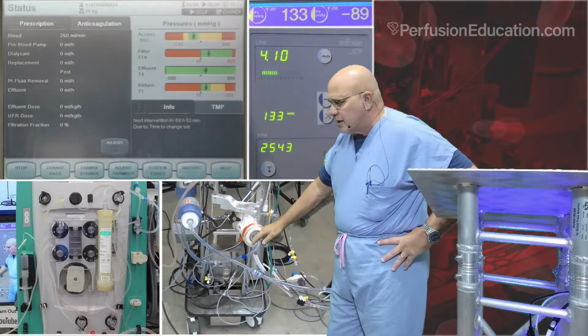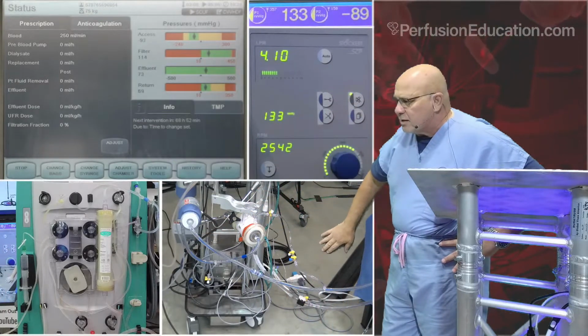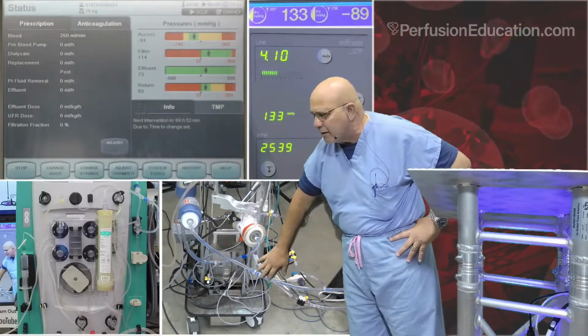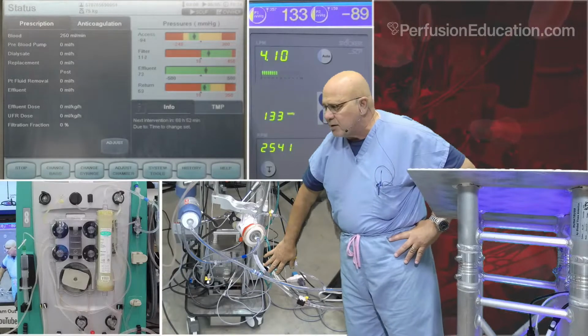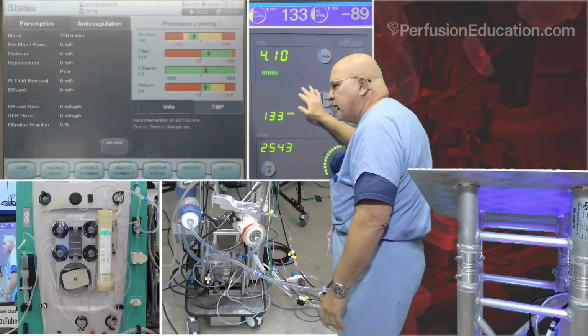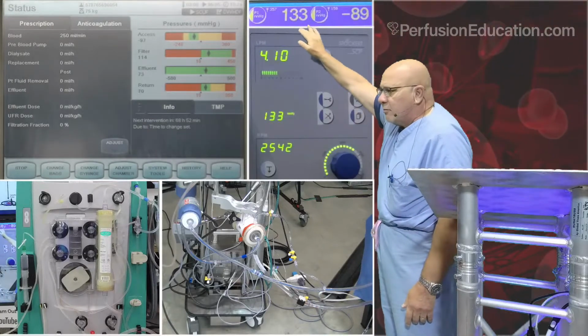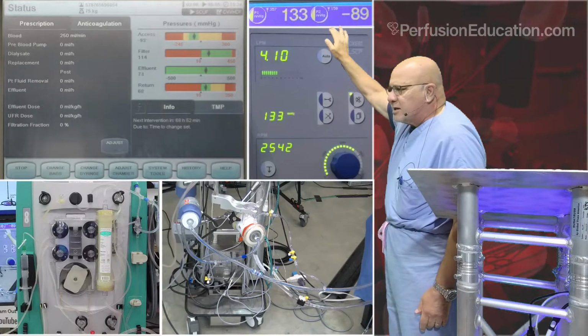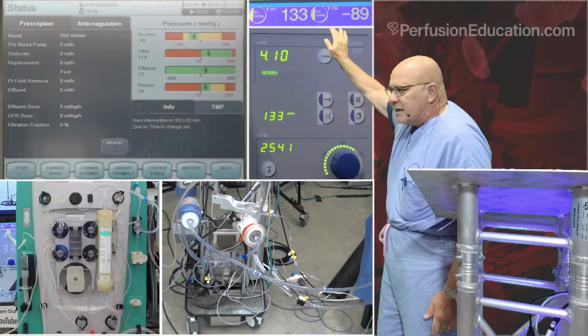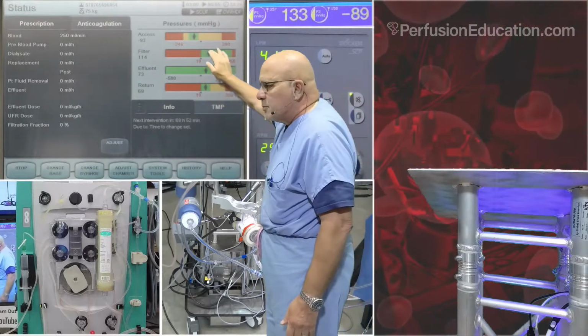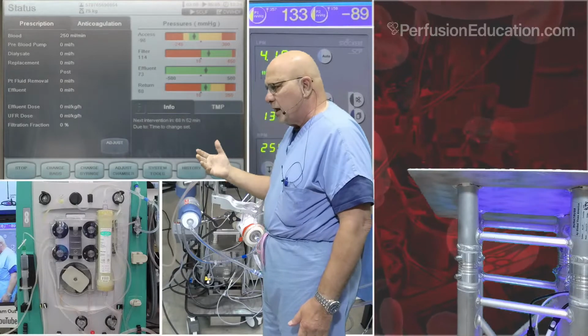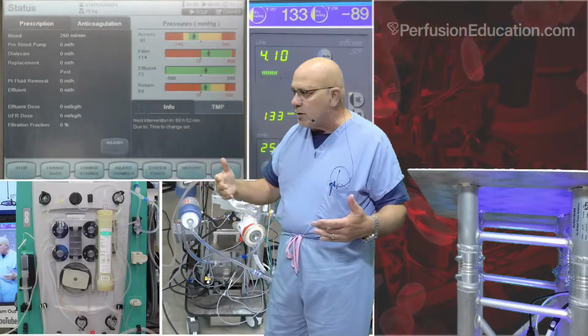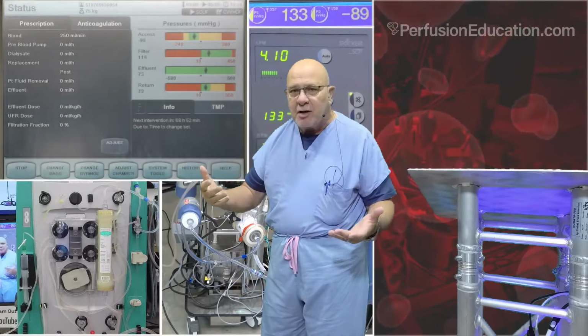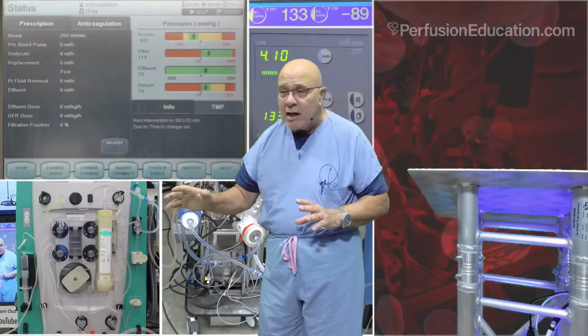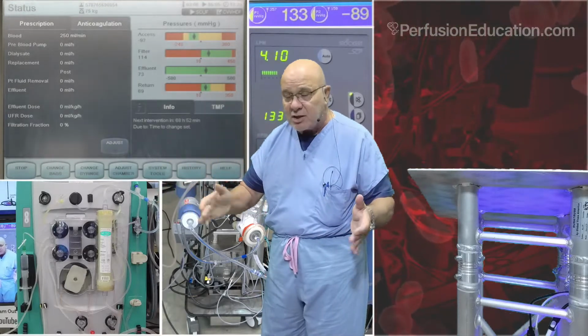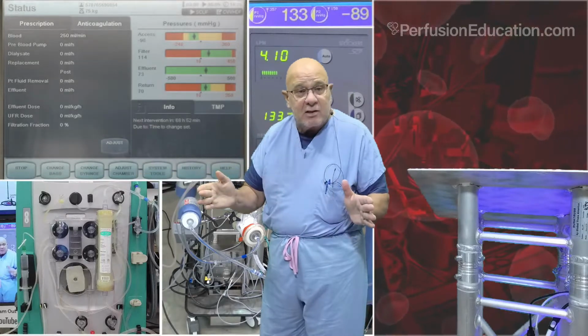Here is our ECMO circuit that's hooked up to our simulator, but we're not going to be working on the ECMO simulator. We're only going to be focusing on this area that you see here where I integrate the CRRT machine. And of course, you have our ECMO flows, and we have our pressures. We have our return pressure, which is 133, and our access pressure, negative 90. But what I want you to notice is your access pressure, which I have set up currently just in a saline bag, designed to sort of simulate what it would be in a temporary dialysis catheter. I'm not running any treatment. I'm only running the blood flow for the sake of this discussion. We may add that as we go forward because those things have impact.